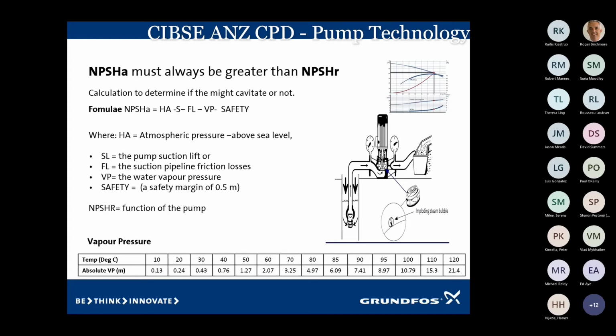When we work with higher temperatures, let's say we're working with 90-degree water, you can see now that the vapor pressure is 7.41, which is a lot higher than 20 degrees. So if our vapor pressure is 7.4, that only leaves us 3 meters off our net positive suction head available. So the likelihood of you being able to lift water at 90 degrees is pretty low. Your pump would have to be pretty close to the water level, and all your losses would be quite low.